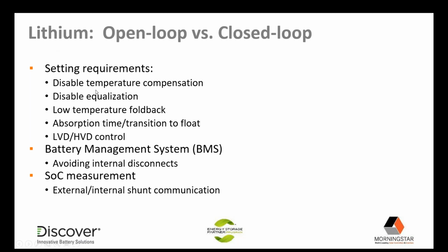These are just a list of many of the things we had to keep in mind when we were generating those settings. These are typical requirements for any lithium battery, but also a lot of behavior specific to where the battery may have internal disconnects triggered, either by high or low cell voltage limits, overcurrent, temperature conditions, and that kind of thing. We wanted to mitigate that if at all possible to avoid internal disconnects. We never want the battery to disconnect from our controller while we're still charging.